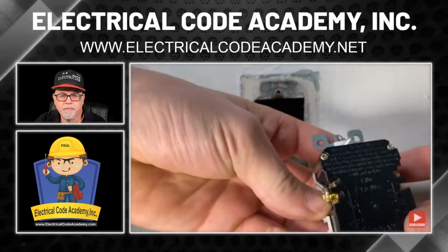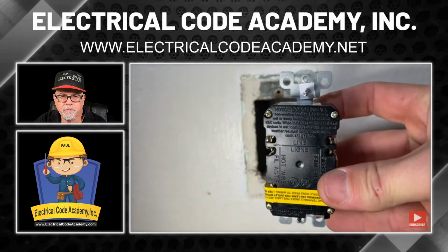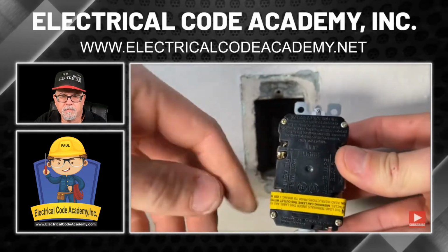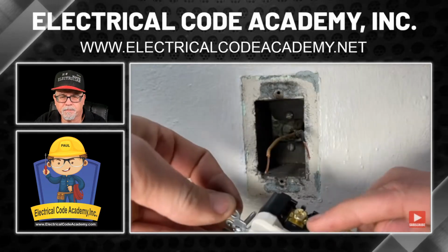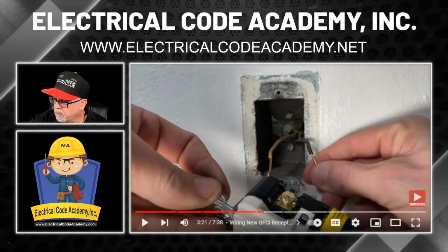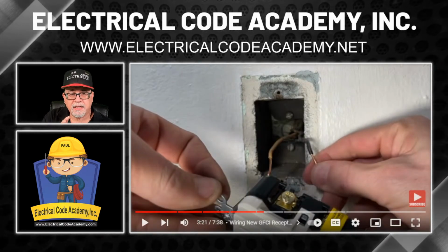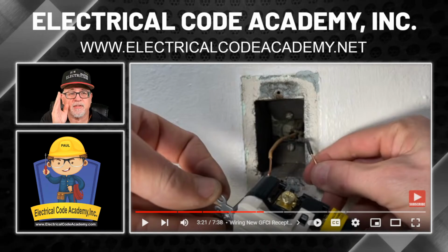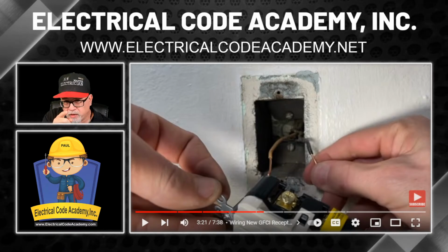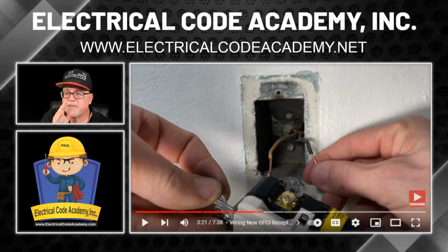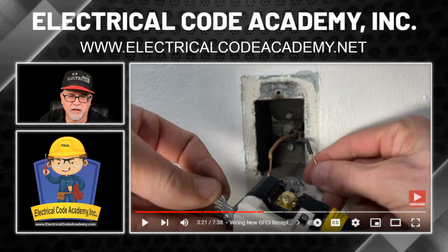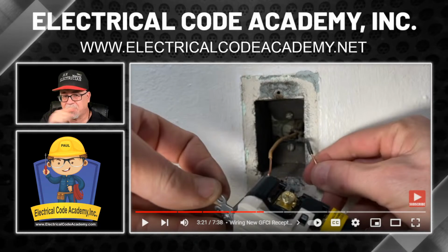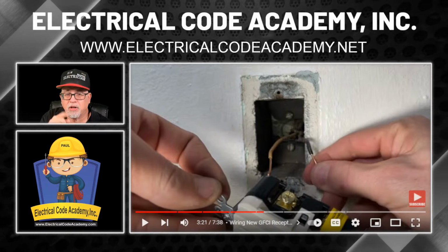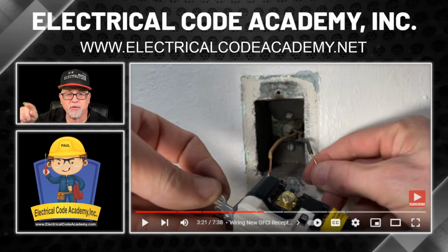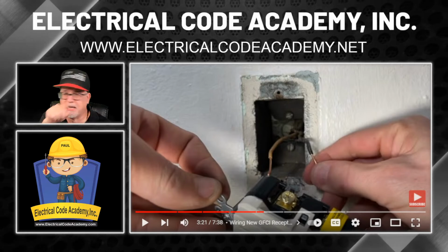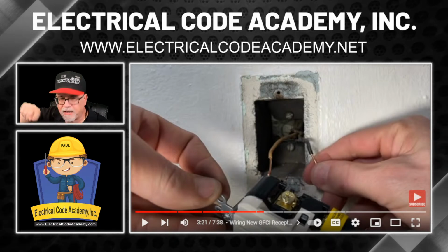Now you'll see we're only using the line portion of the GFCI. The load portions underneath this label for this instance will not be used. Now remember, if you're doing this, and we'll look at the code later, if this is the first receptacle and there was more than one cable in the box, going to multiple receptacles downstream, then you would be doing the line in from the source, and the load would be what's going out to the other receptacles downstream. So you're feeding into the device and then out of the device downstream.